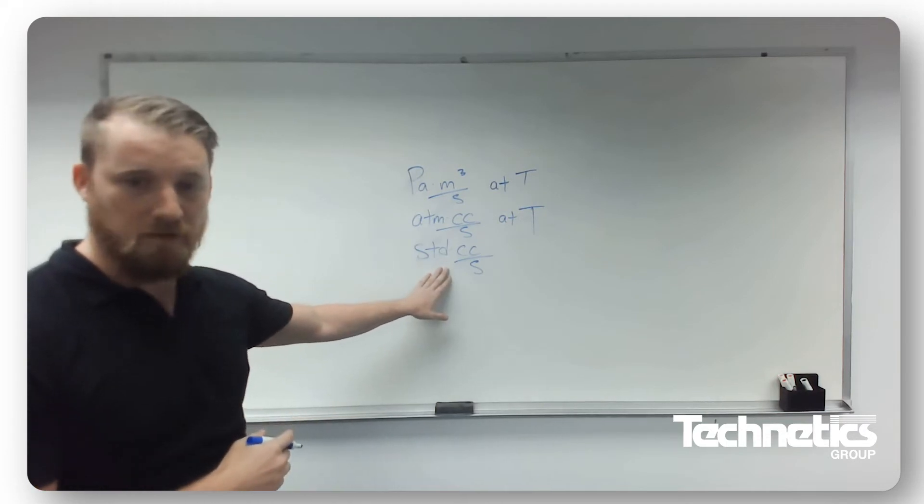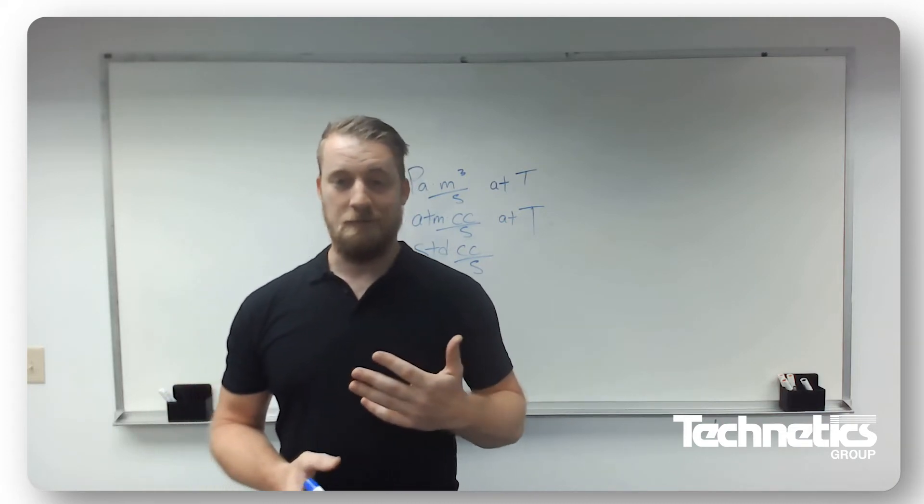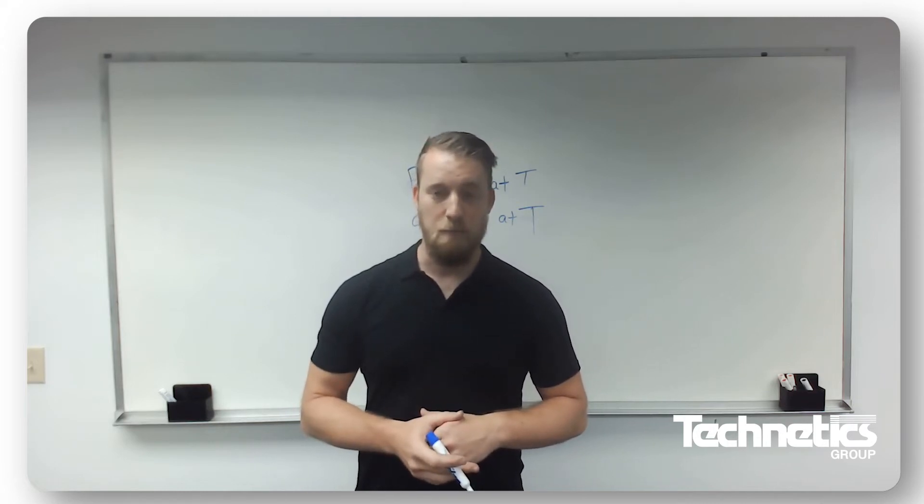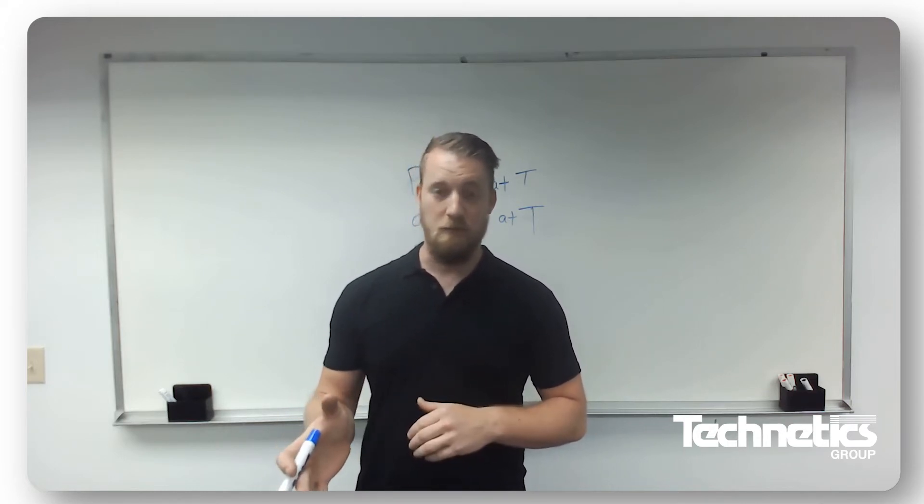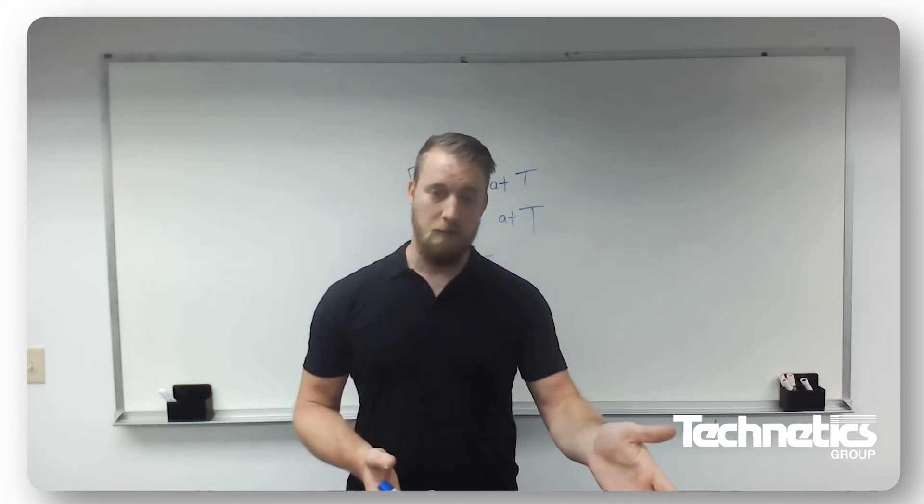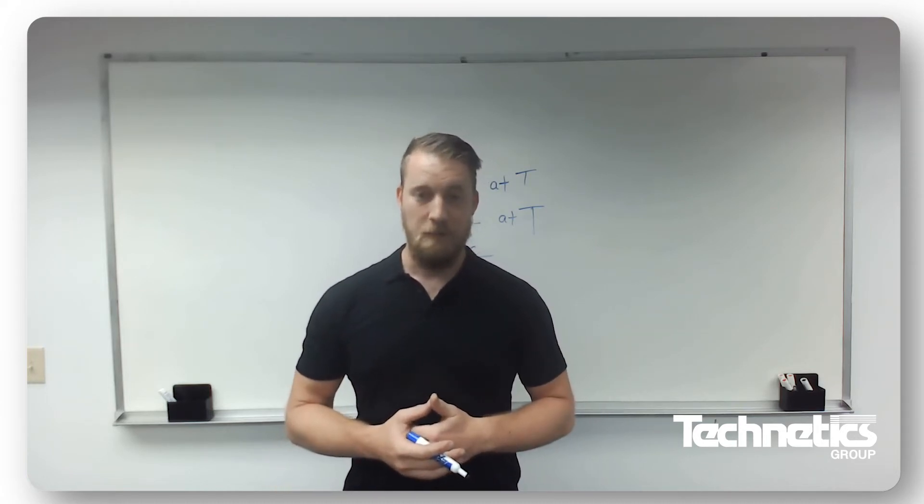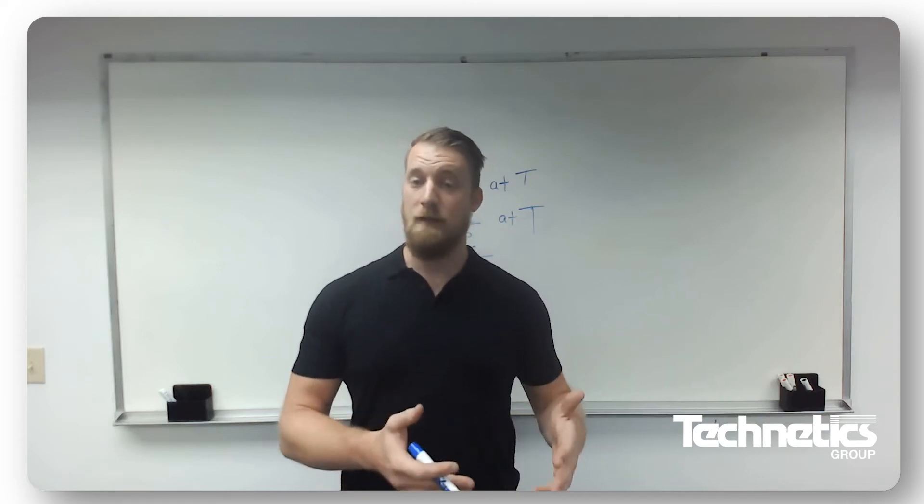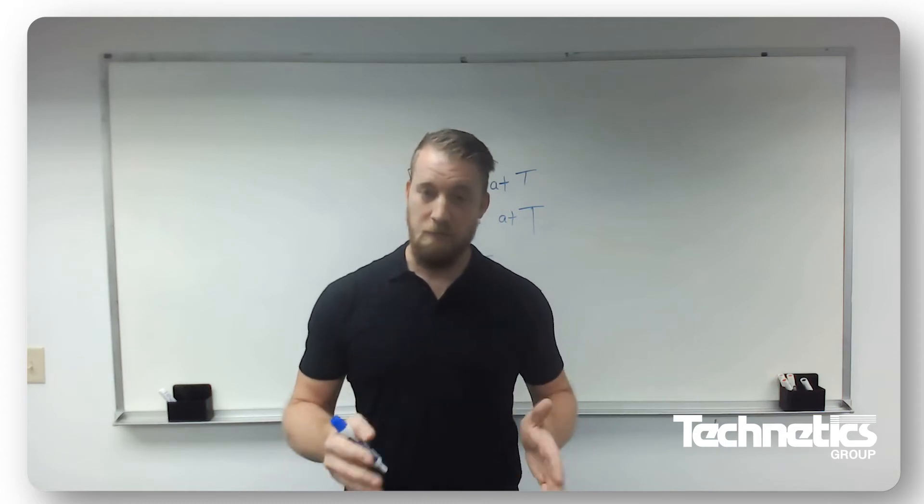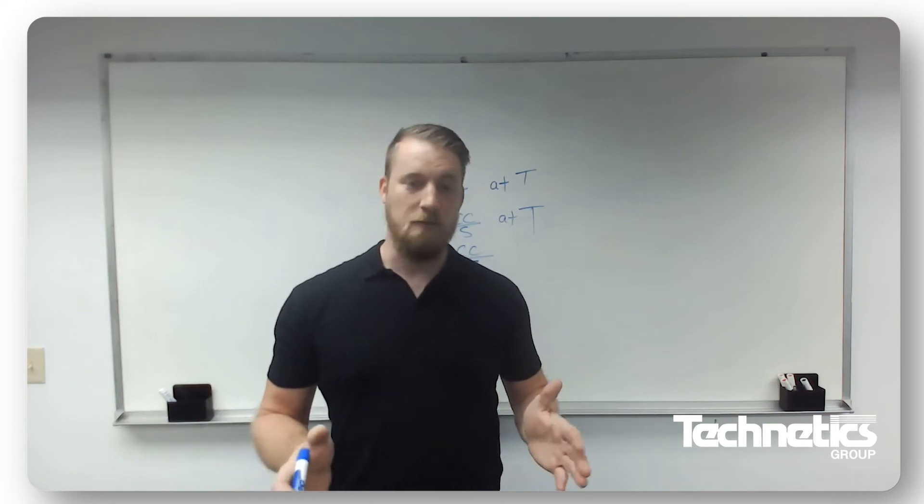Now, standard cc per second is a little bit different because what this is implying is that you're following a standard. And if you are following, say, NIST, the National Institute of Standard and Technology, standard temperature and pressure according to that is 0 degrees Celsius and 101.325 kilopascal. If you're following IUPAC, their standard atmospheric conditions are 25 degrees Celsius and 100 kilopascal. And if you're following ISO, ISO has so many different standard temperatures and pressures that you even have to specify which ISO standard you're following for that application. And once we have all this information, then we're well on our way to designing a solution that will fit your needs.